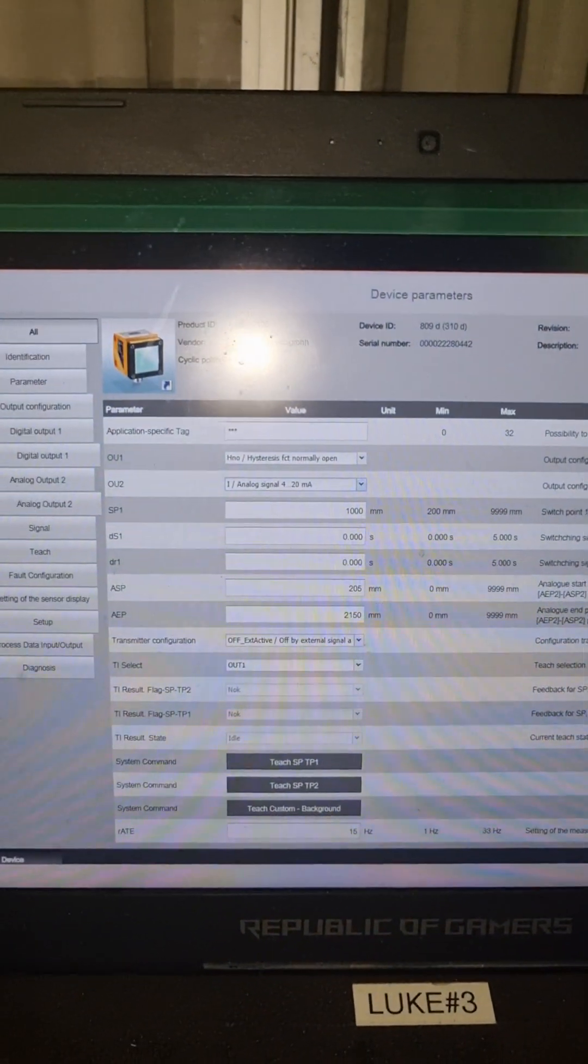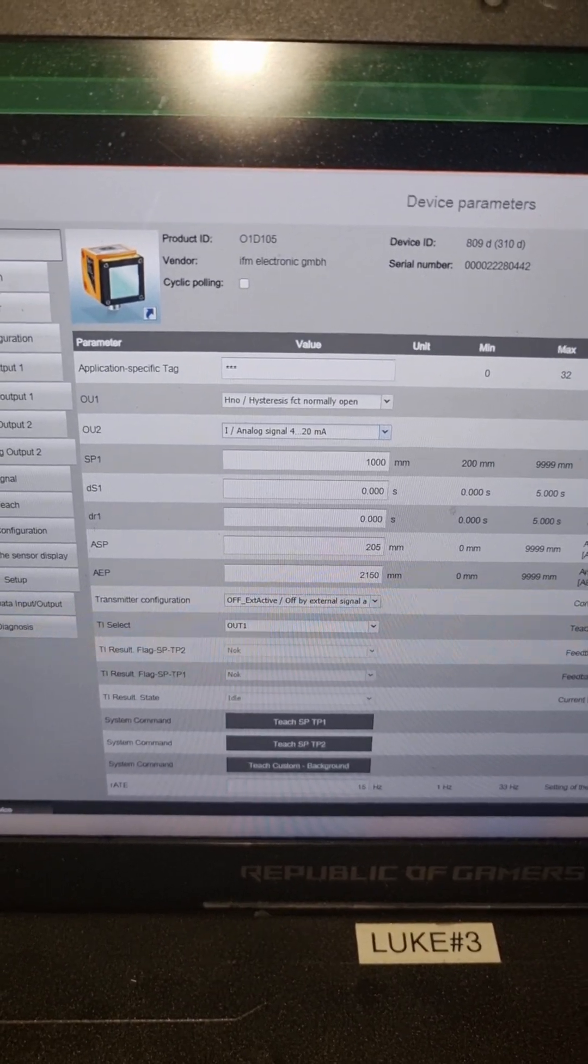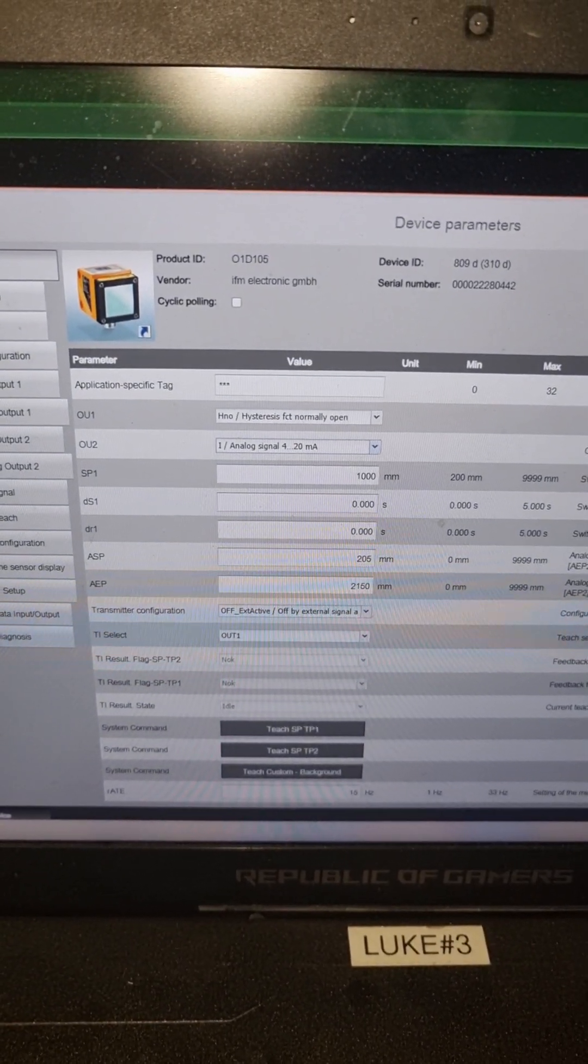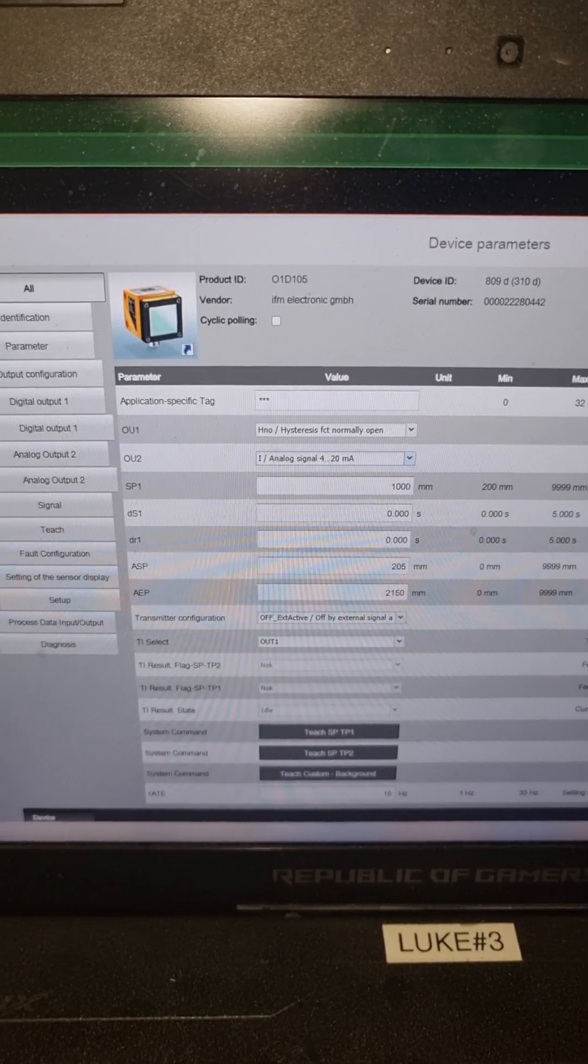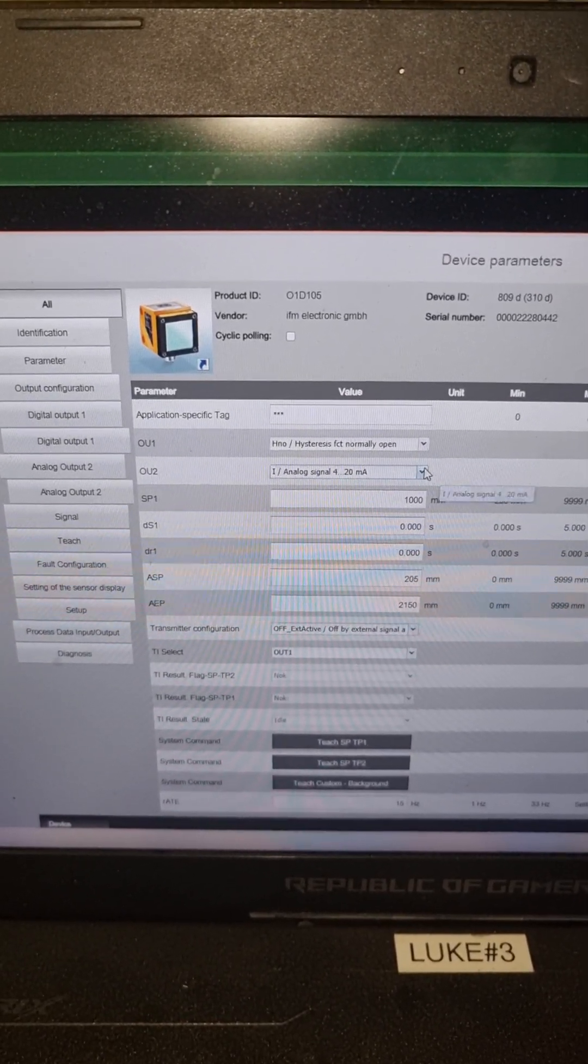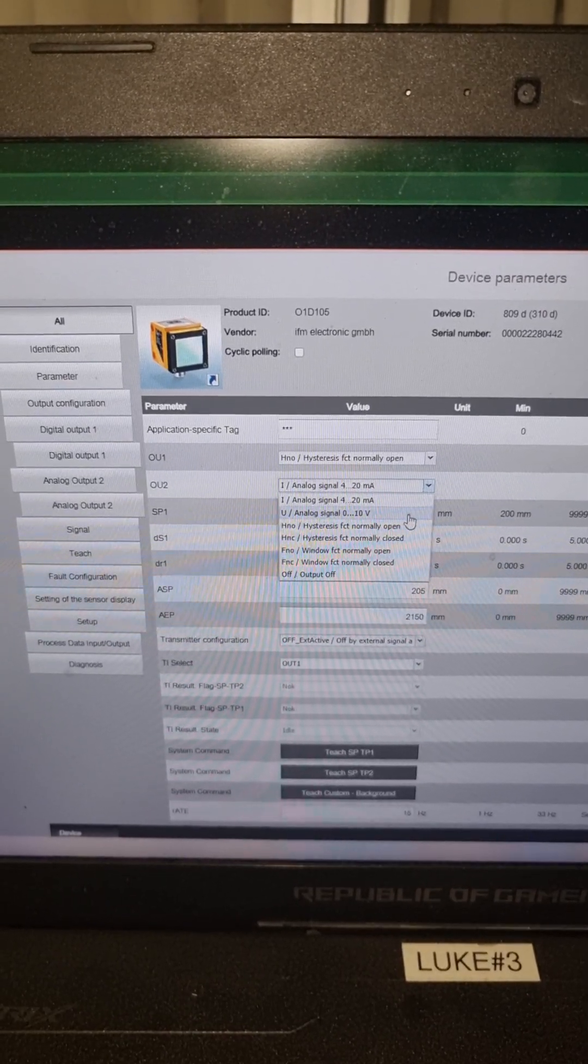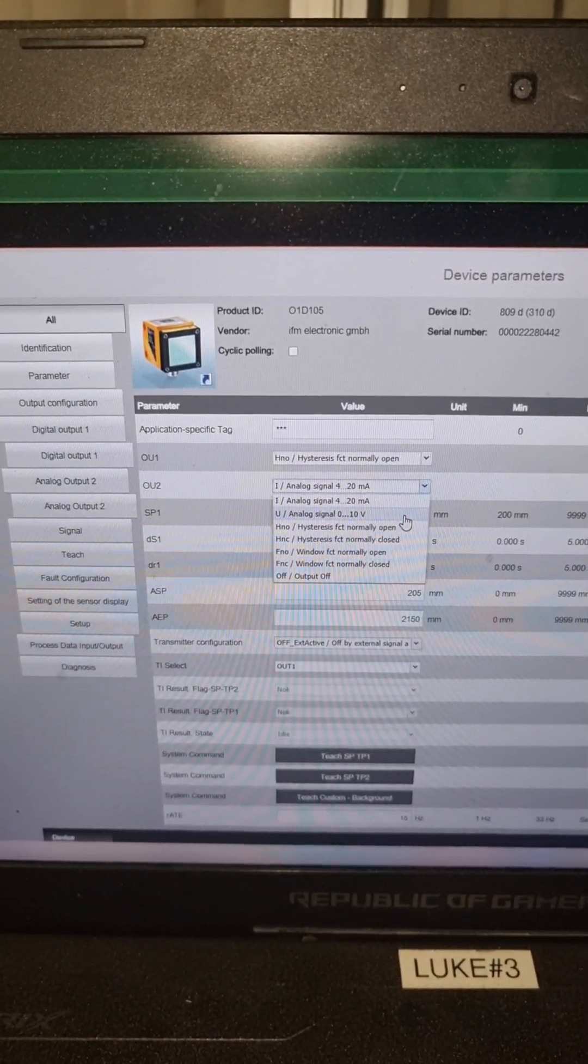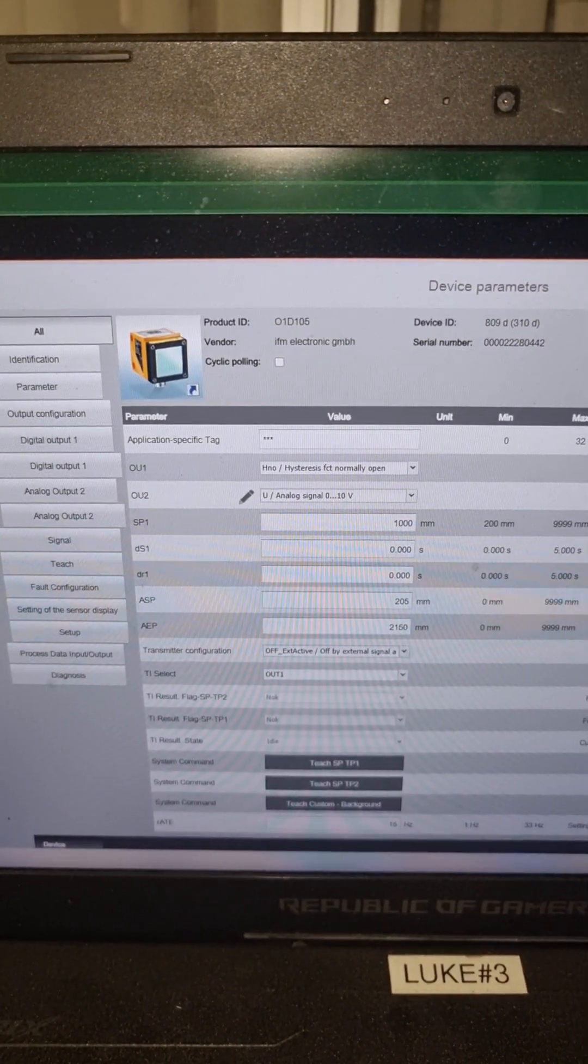Next little check looking on IO-Link line recorder device, checking the configuration. This here has been set to 4 to 20 milliamps. We'll just change that back to 0 to 10 volts and apply that to the sensor.